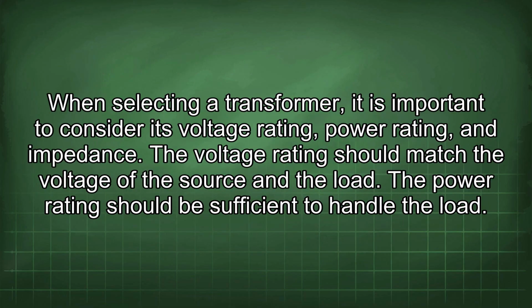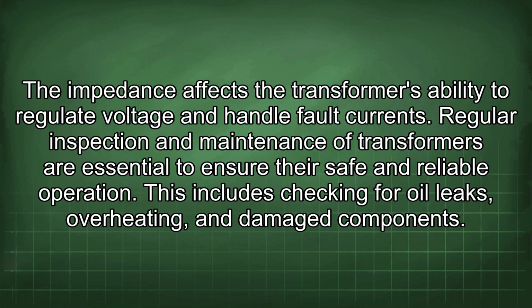When selecting a transformer, it is important to consider its voltage rating, power rating, and impedance. The voltage rating should match the voltage of the source and the load. The power rating should be sufficient to handle the load. The impedance affects the transformer's ability to regulate voltage and handle fault currents.